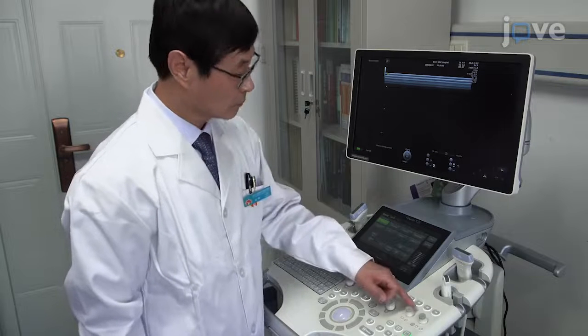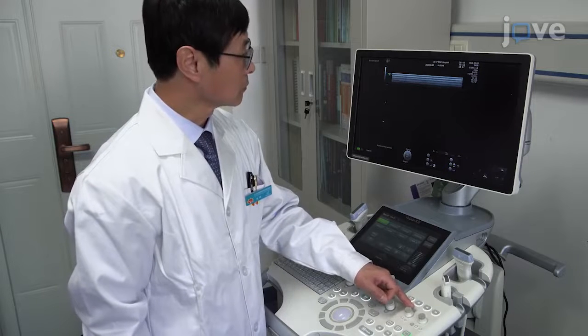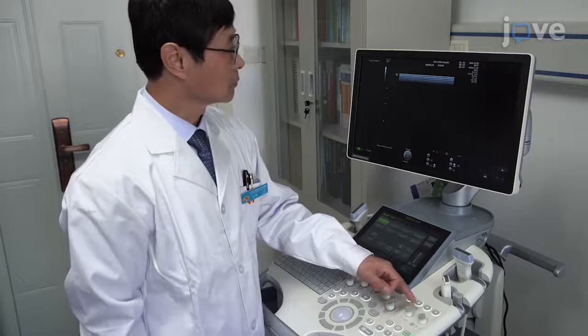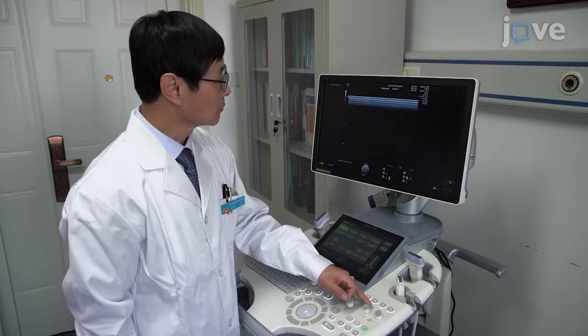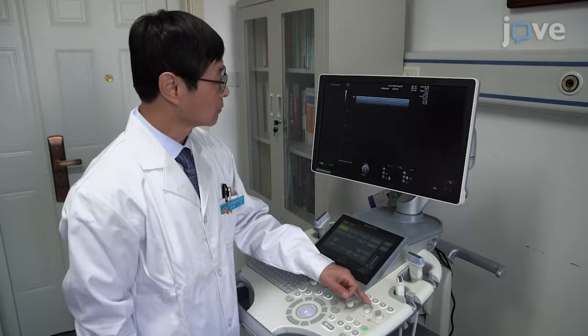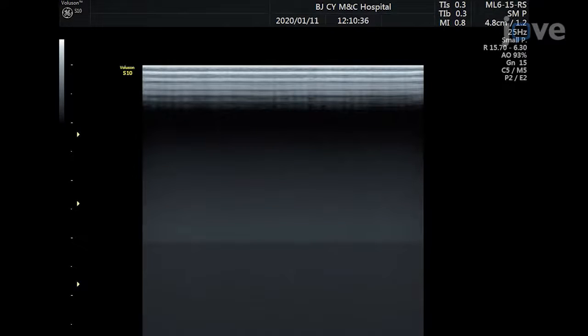To optimize the imaging settings for an examination when no lung ultrasound preset is available, select one of the Small Parts presets and use the Depth button to adjust the depth to 4 to 5 centimeters. Use the Focus Zone button to select one or two focuses and adjust the focus close to the pleural line.